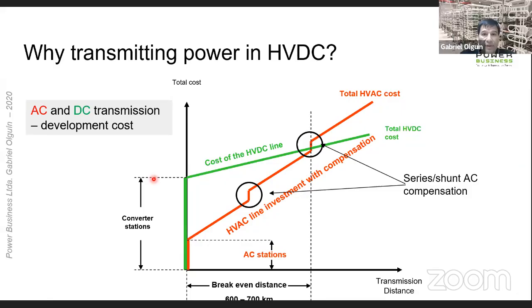So why transmit power in direct current? This figure shows the economics of HVDC as compared to HVAC. The figure shows the development cost of transmission line in AC in red and in DC in green. HVDC converters are more expensive than AC stations. However, the per kilometer cost of the DC line is less than the cost per kilometer of an AC line.